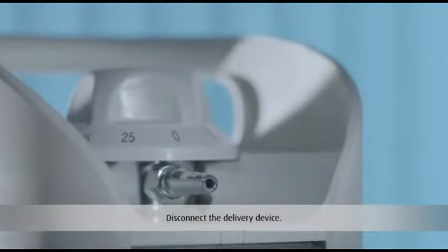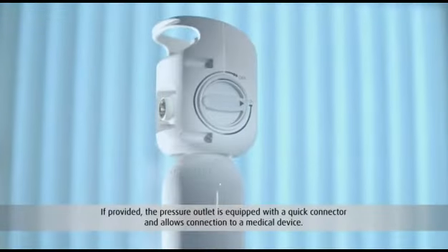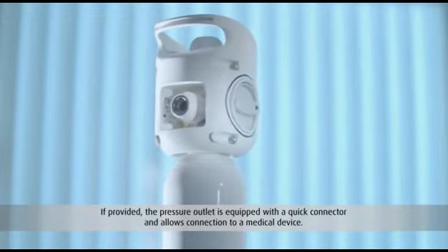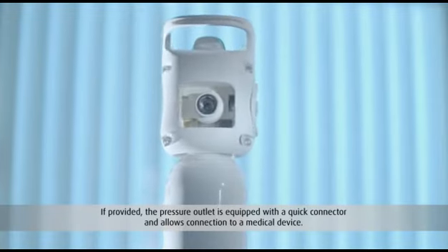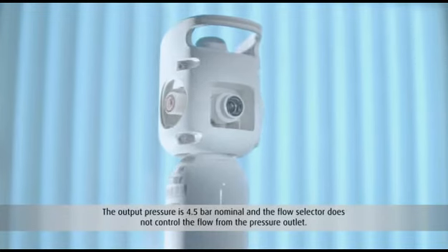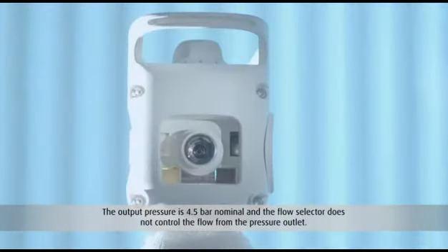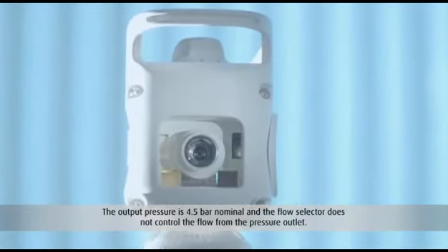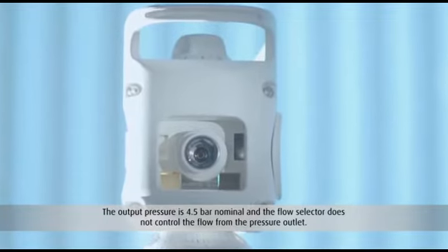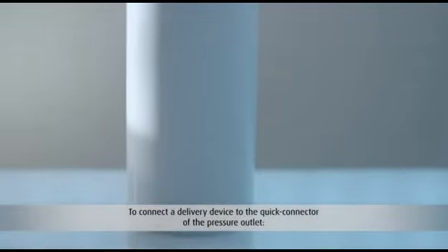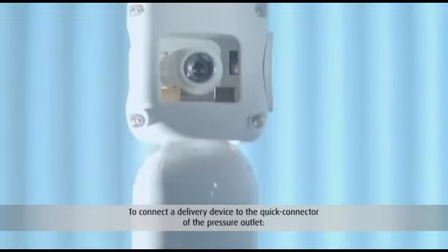Disconnect the delivery device. If provided, the pressure outlet is equipped with a quick connector and allows connection to a medical device. The output pressure is 4.5 bar nominal and the flow selector does not control the flow from the pressure outlet.